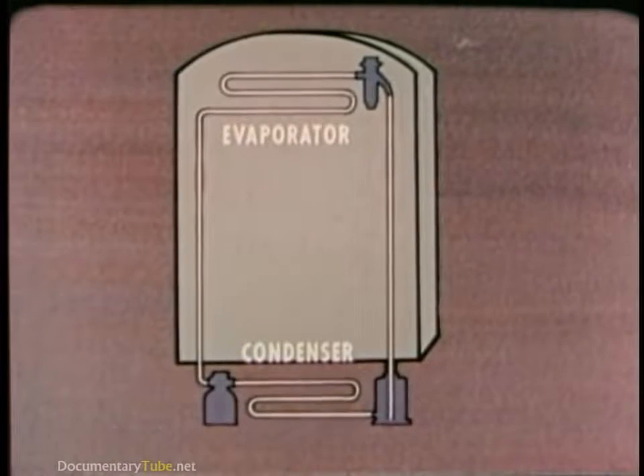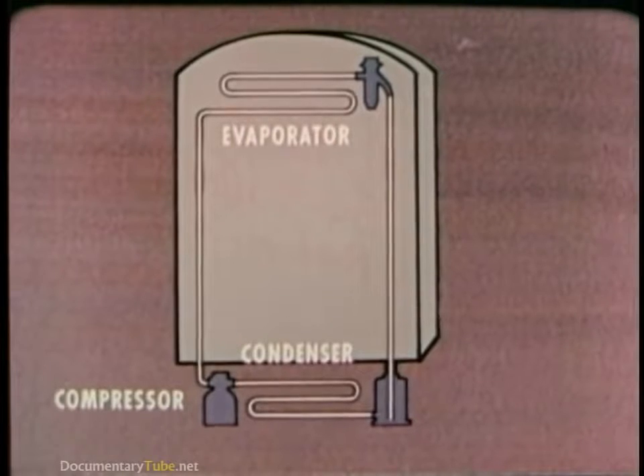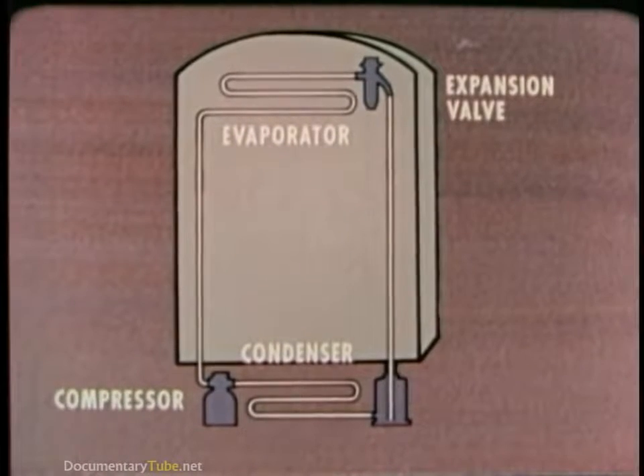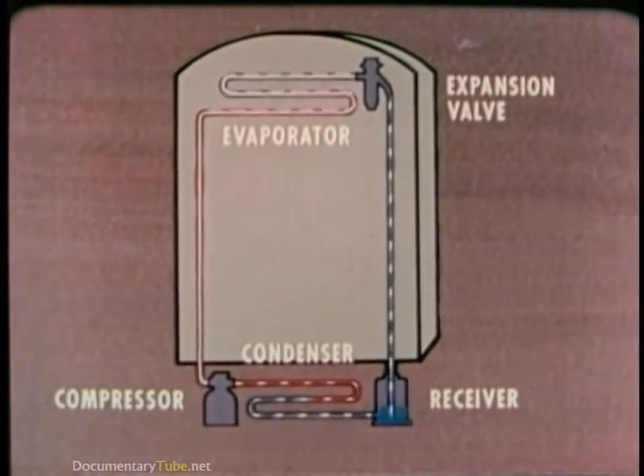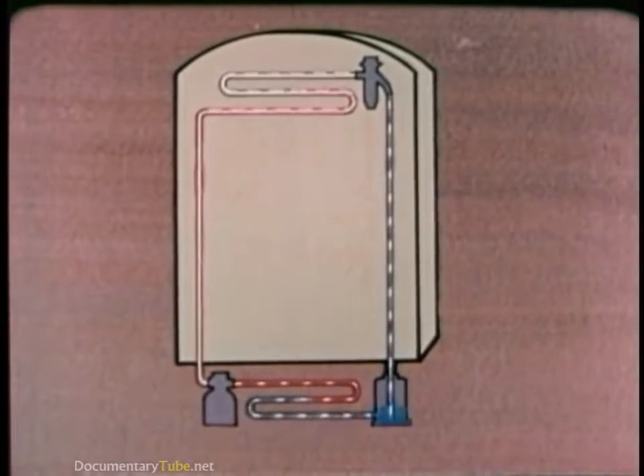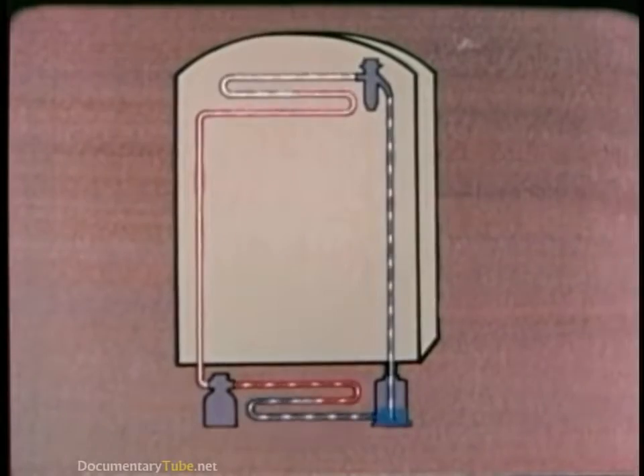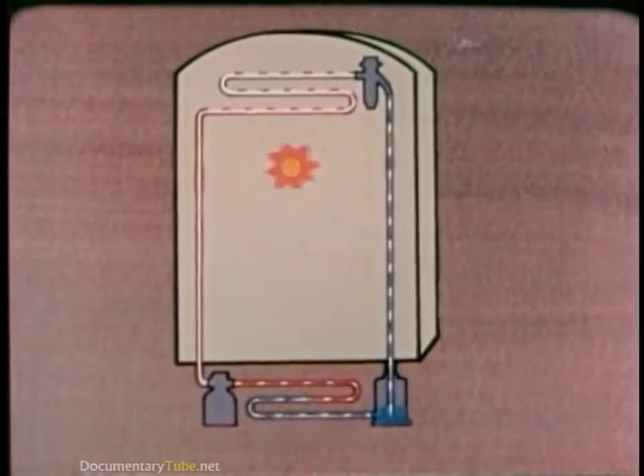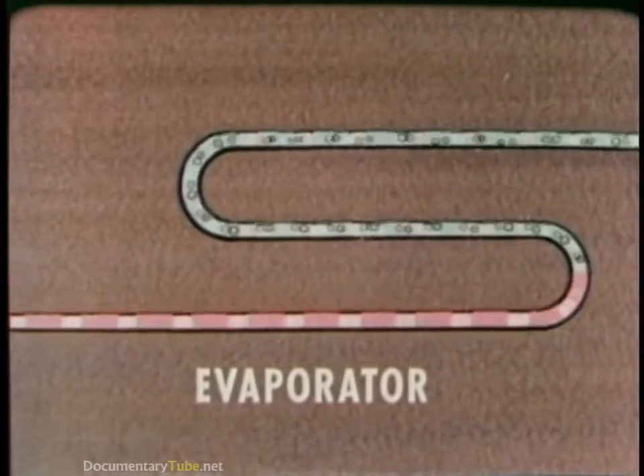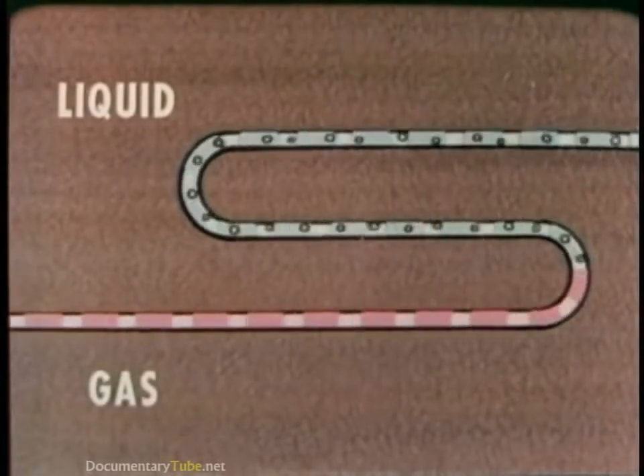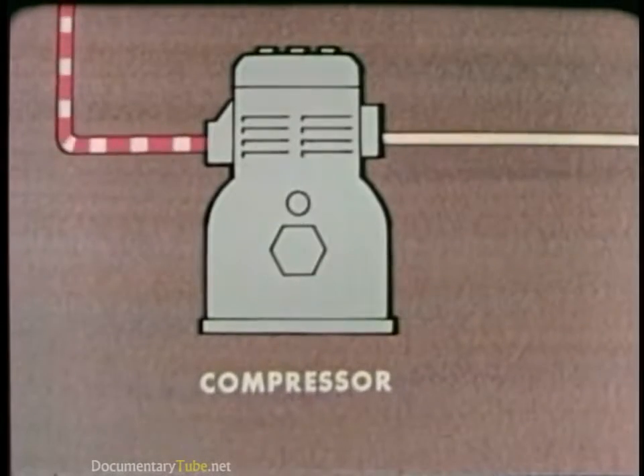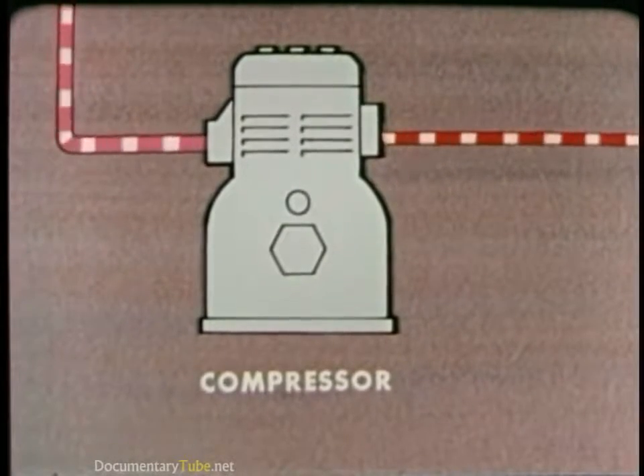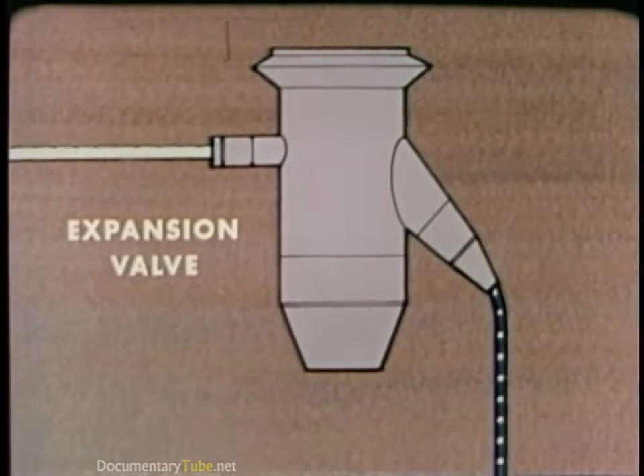Also in the system are the compressor, which is a pump, the expansion valve, and in many systems the receiver, a kind of storage tank. A chemical substance called the refrigerant flows through the system. It's the refrigerant that picks up BTUs of heat from inside the box and discards them outside. In the process, the refrigerant changes from a liquid to a gas. Then in the condenser it changes back to a liquid. At the same time, the pressure increases in the compressor and decreases in the expansion valve.